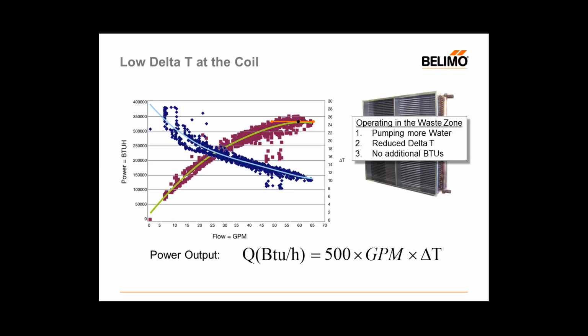And so the idea of delta T management is by examining delta T and forcing slower flows through there that we can utilize the lower end. Not that we'll always be able to use 47 gallons a minute, but more like we don't ever need to be at 65 gallons a minute. There's a misconception that this is a full load scenario and that there's no advantage to delta T limiting at partial loads, and that's just not true.